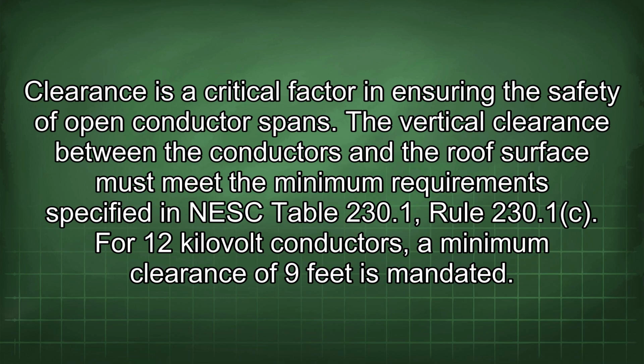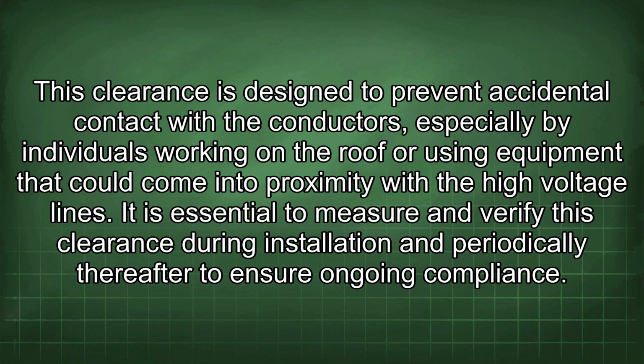The vertical clearance between the conductors and the roof surface must meet the minimum requirement specified in NESC Table 230.1, Rule 230.1. For 12 kilovolt conductors, a minimum clearance of 9 feet is mandated. This clearance is designed to prevent accidental contact with the conductors, especially by individuals working on the roof or using equipment that could come into proximity with the high voltage lines. It is essential to measure and verify this clearance during installation and periodically thereafter to ensure ongoing compliance.